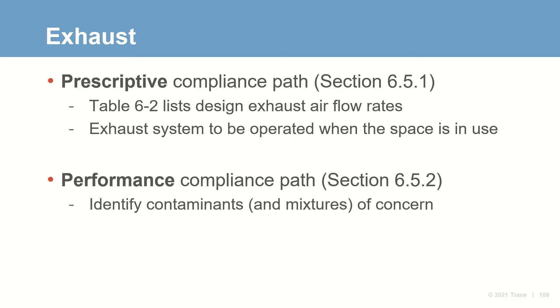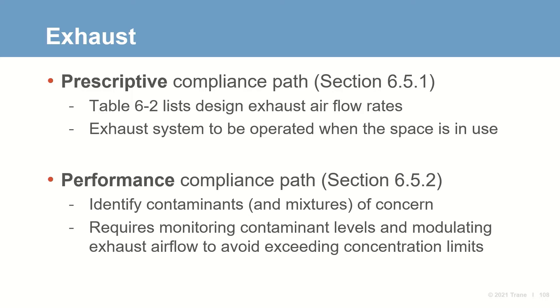On the other hand, the performance path is similar to the IAQ procedure. It requires you to identify all the contaminants of concern and their concentration limits. The exhaust system must be designed to actively monitor these contaminant levels and modulate the exhaust air flow to avoid exceeding the concentration limits.